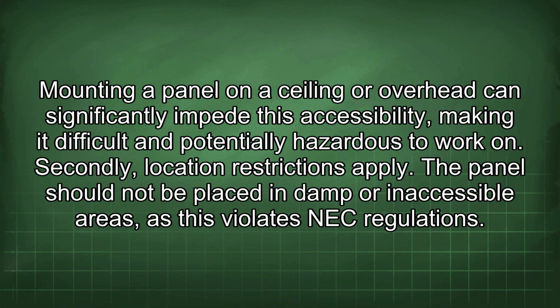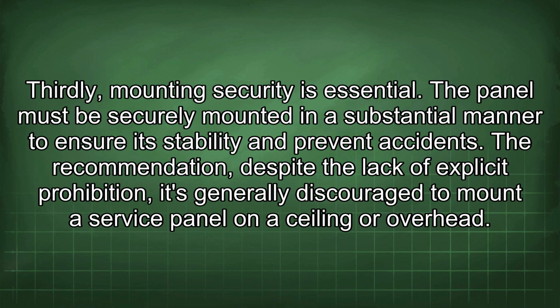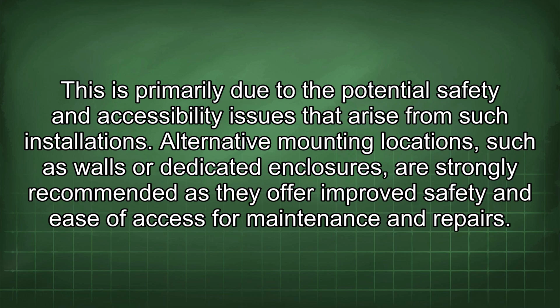The panel should not be placed in damp or inaccessible areas, as this violates NEC regulations. Thirdly, mounting security is essential. The panel must be securely mounted in a substantial manner to ensure its stability and prevent accidents. The recommendation: despite the lack of explicit prohibition, it's generally discouraged to mount a service panel on a ceiling or overhead. This is primarily due to the potential safety and accessibility issues that arise from such installations. Alternative mounting locations, such as walls or dedicated enclosures, are strongly recommended as they offer improved safety and ease of access for maintenance and repairs.